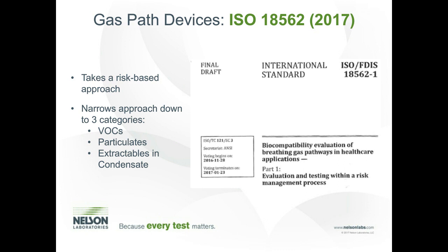because people might argue that, oh, they don't really contact the body, but they do. It's external communicating. It contacts it through the gas. So ISO 18562 was made to address this issue. It came in its final form just this year in March. The beauty about this series, there's four parts to it.